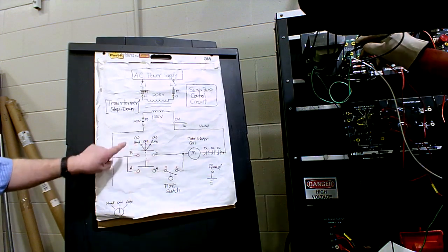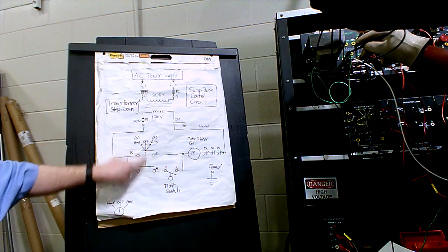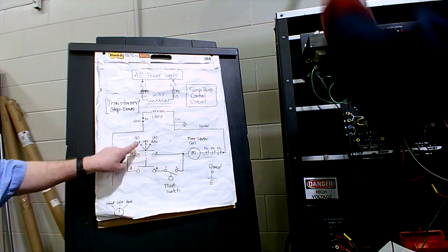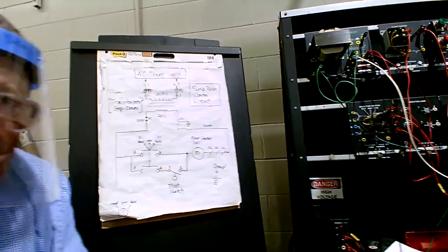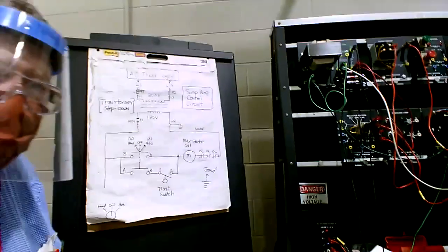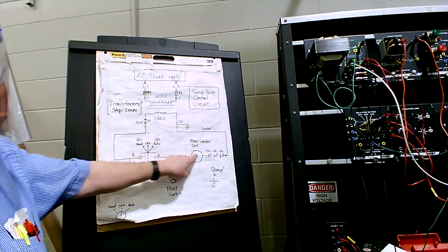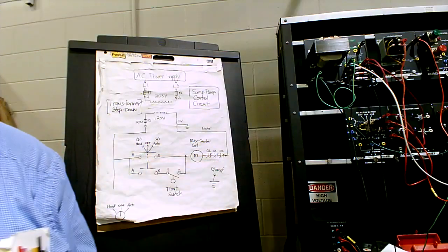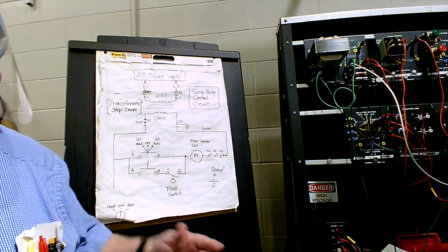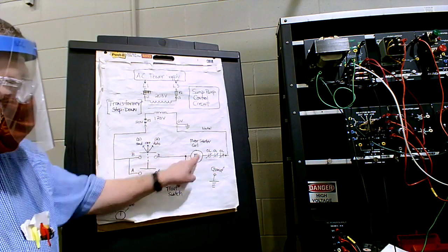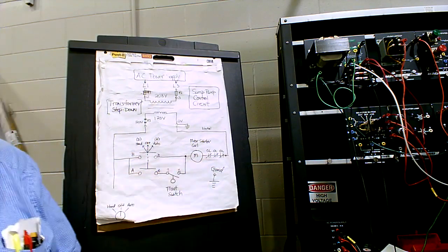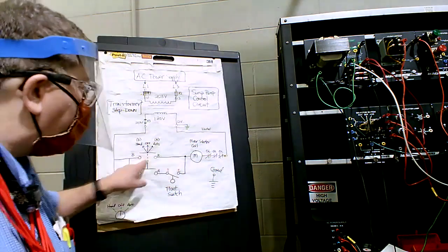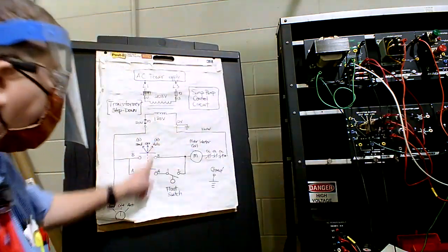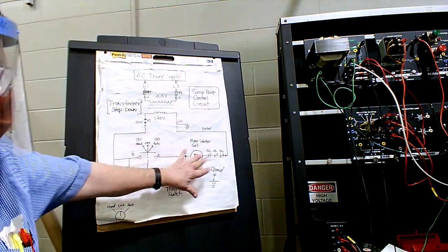Here's what the circuit does. You're taking the 120 volt and you're going to a selector switch. The selector switch is a 3-position. When you put it to the left for hand, here's what you get. The power goes straight to the motor starter, and the motor comes on, and the pump's just going to run constantly with nothing controlling it other than the switch. That's going to be in hand. That's going to be for a pump motor to pull water out of a pit for waste treatment. Now, if you put it in the off position, it's never going to run. Both of them are going to be open, and the pump motor's never going to run.